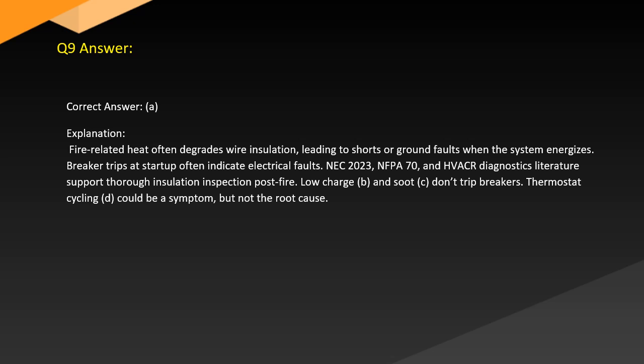Answer. Correct answer: A. Explanation. Fire-related heat often degrades wire insulation, leading to shorts or ground faults when the system energizes. Breaker trips at startup often indicate electrical faults. NEC 2023, NFPA 70, and HVACR diagnostics literature support thorough insulation inspection post-fire. Low charge, B, and soot, C, don't trip breakers.